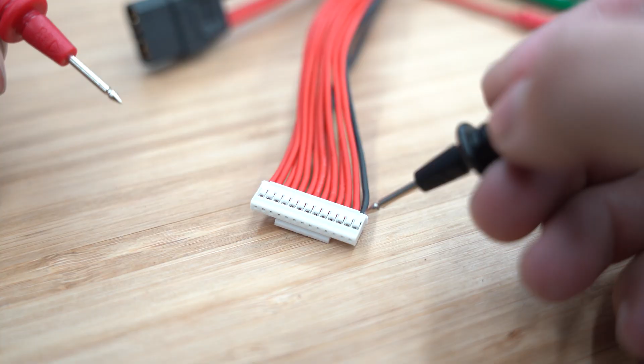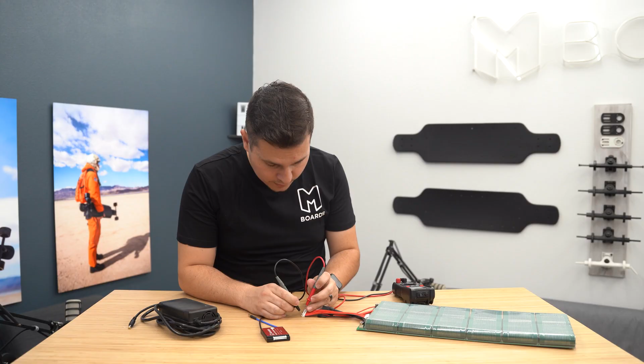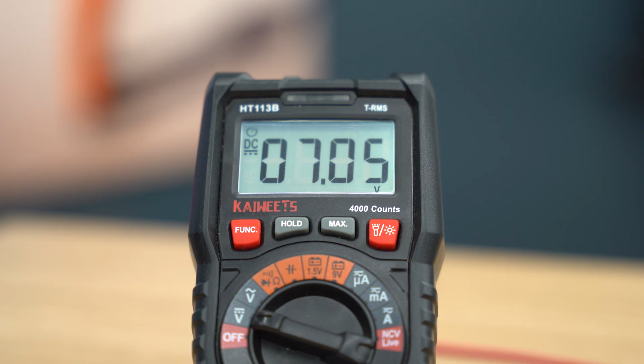Luckily, I'm using a transparent series battery from our shop here, so getting access to these cables is very easy. What we're going to do is probe each individual pin. The easiest thing is we put our black probe on our black pin, and then we'll take our red probe and put it on the very first red pin, and we will get 3.53 volts. That's the voltage of our very first group. Now if I continue moving along into each individual pin, it's saying 7.06 — that's group 1 and 2 added together. The next pin is 10.59 volts, which is group 1, 2, and 3 added together. And I can go all the way down the list until I get to 42.3, so you'll get 12 different values.